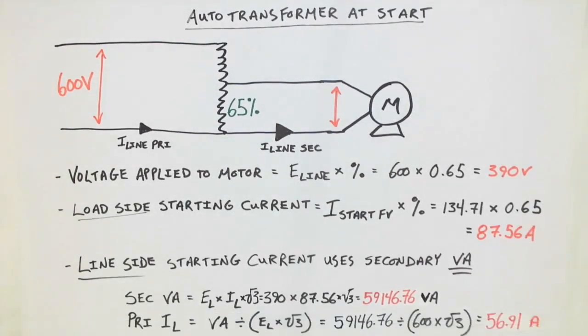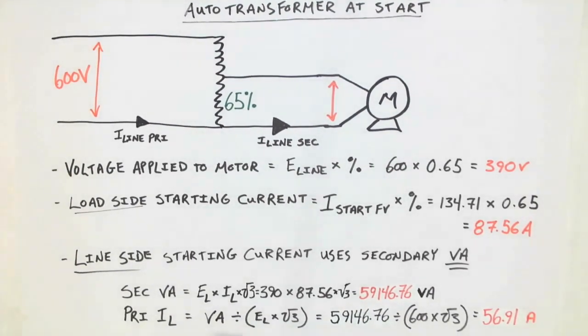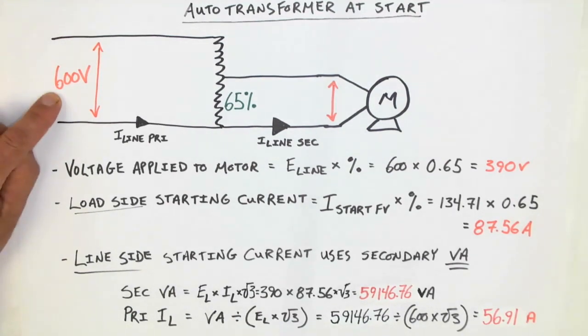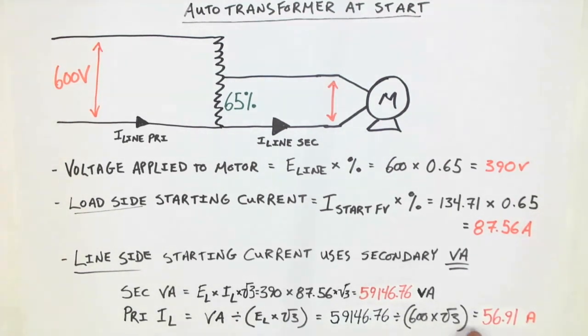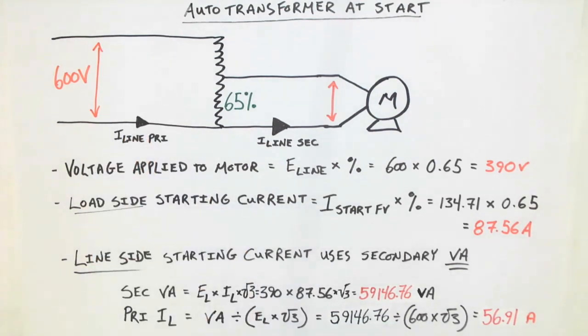In order for us to calculate that primary value, we take our VA and divide it by the E line times root 3. The E line over here is 600 volts, and with root 3, this renders 56.91 amps. In this way, an autotransformer starter can offer the same benefits as a primary resistor. However, it's more efficient because we're not losing watts due to heat, and we have a lower current on the supply side of the autotransformer starter.